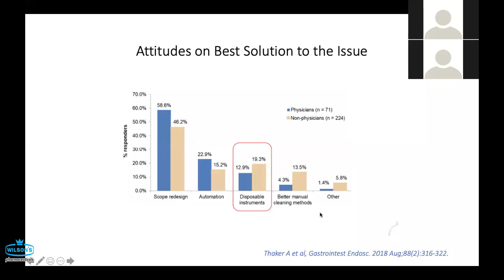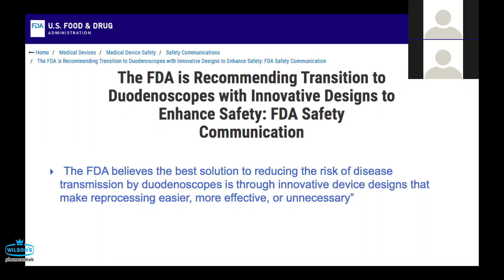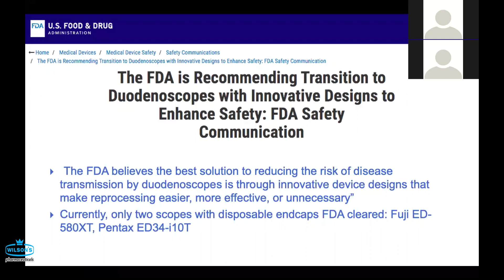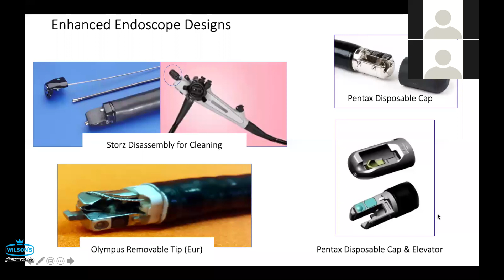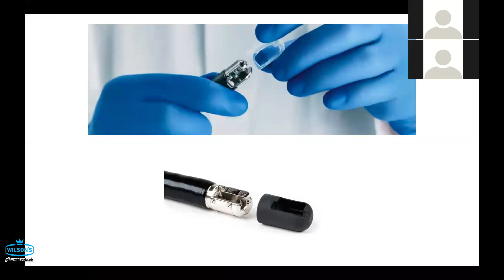So the FDA is recommending transition to duodenoscopes with innovative designs to enhance safety. And this is the FDA's safety communication. They believe the best solution to reducing the risk of disease transmission by duodenoscopes is through innovative device designs that make reprocessing easier, more effective, or unnecessary, and less dependent on human error. Currently there are some designs available, though none of them is perfect. You have an Olympus removable cap, you have a Pentax disposable cap with an elevator, and so on. And there is another one. This is the type of disposable cap which you can change from procedure to procedure.